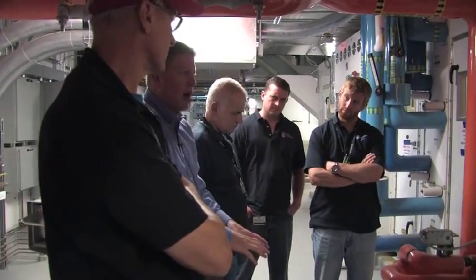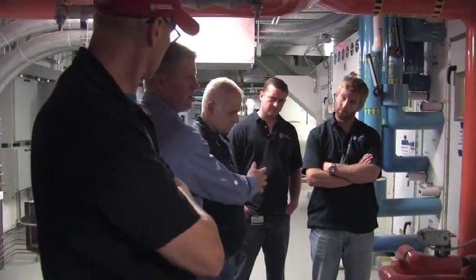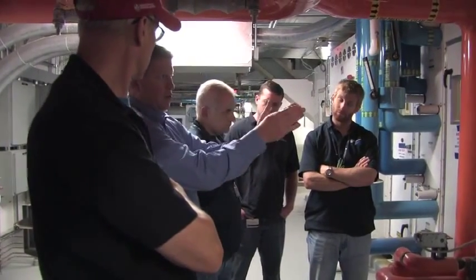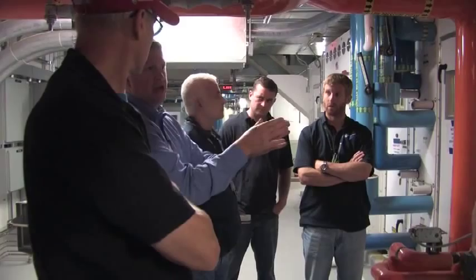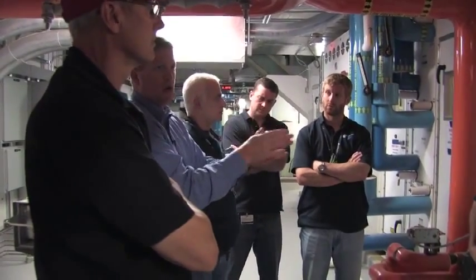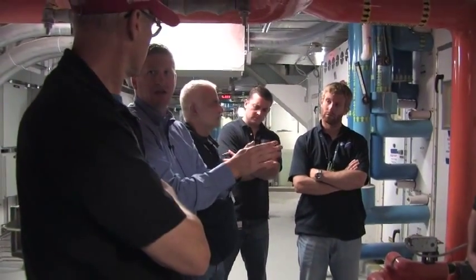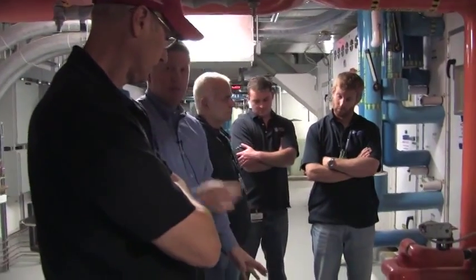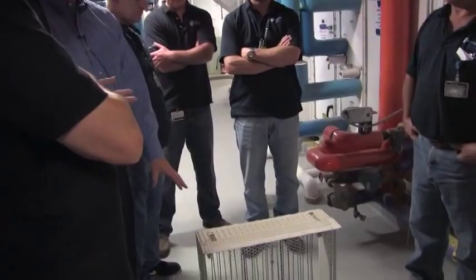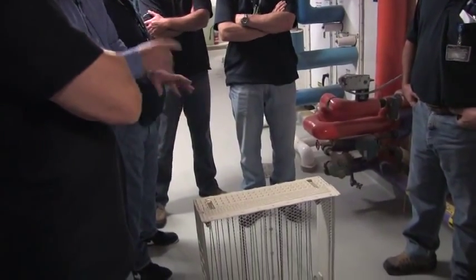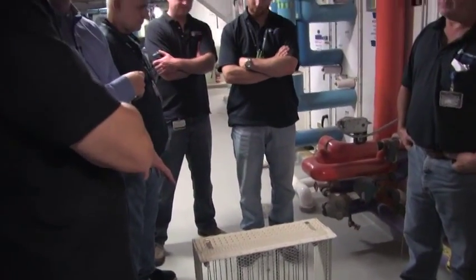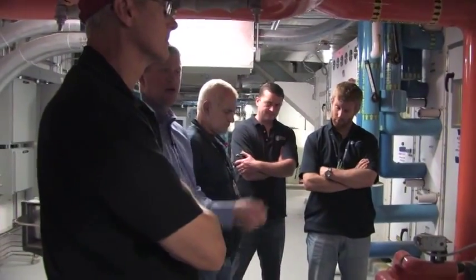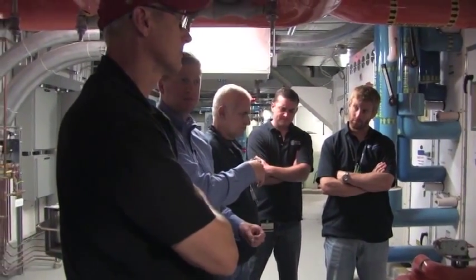You can lose power. It doesn't mean you're going to dump all the particles. Without the power on, that's a MERV 8 filter. With the power on, it's the equivalent of a MERV 15. So what the purpose of this is, you're only paying the pressure drop of a pre-filter, a MERV 8 filter. So the advantage of this is your HEPA filter should last longer. You're going to catch more stuff here. They're going to last longer.